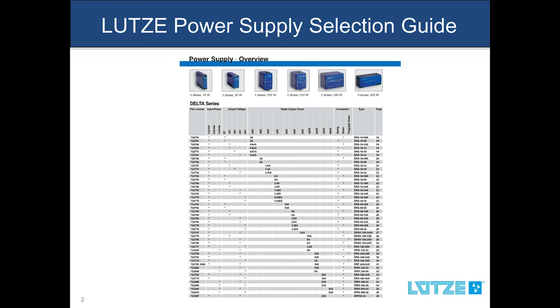So for example, I need 120 watts of output power rated for 24 volts, which brings me to the 5 amp unit. Here you have the selected 24 volt 5 amp power supply rated for 120 watts. Moving to the right, you can see that there is a fixed and a pluggable screw terminal option available. Depending on your preference, you choose the appropriate terminal option. This gives you the LUTZE part number on the left-hand side. The column on the right shows you the page where the detailed specs can be found in this brochure.